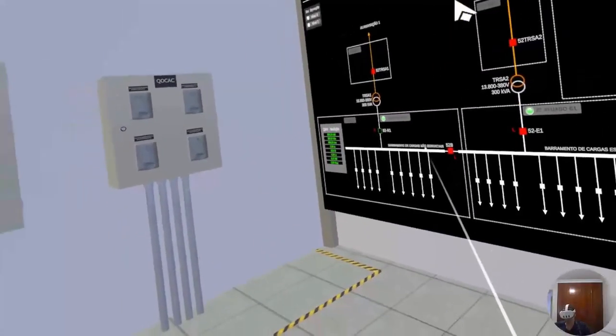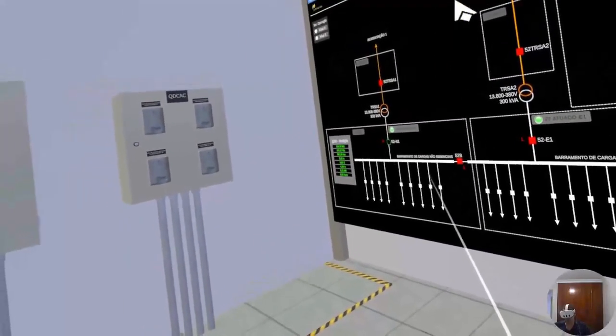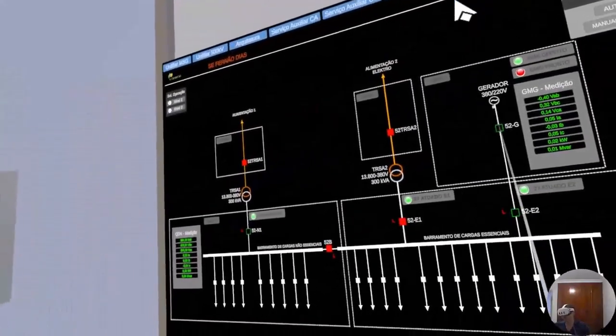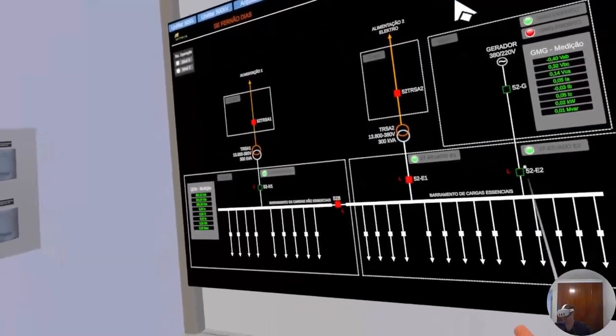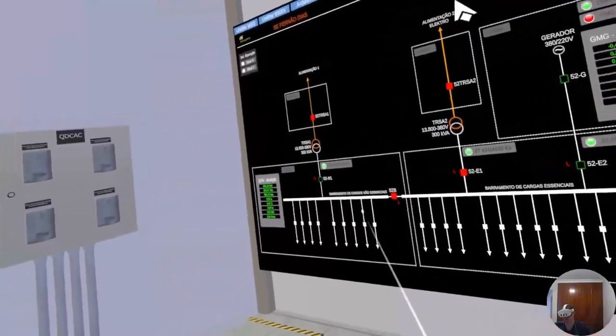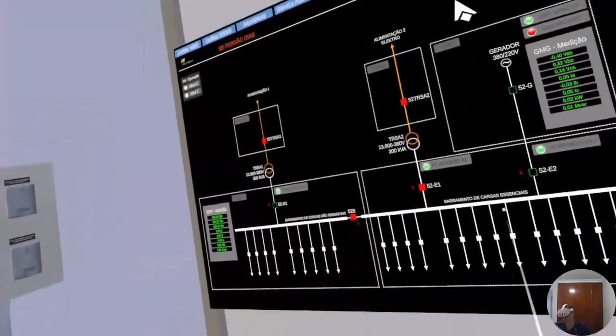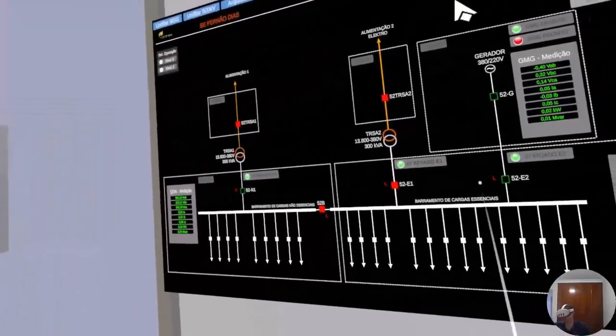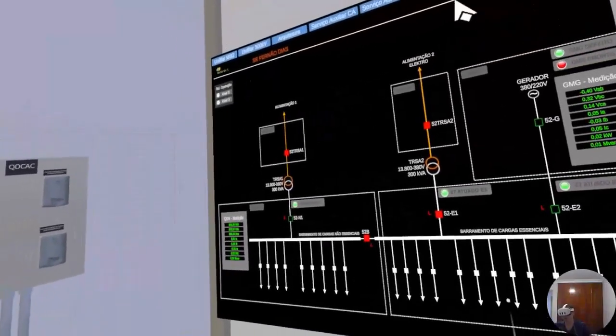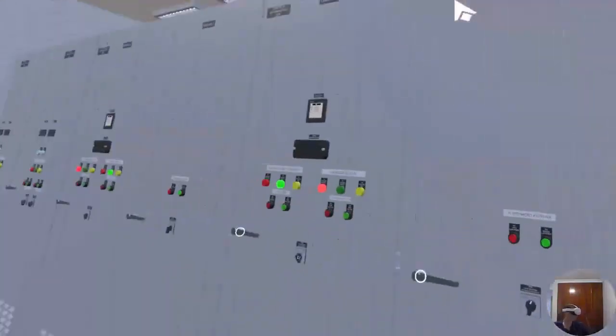Because otherwise, I'll be with the non-essential loads. I run the risk of overloading the diesel, so it will start the moment that I close this circuit breaker here. It will take the load, it could cause an overload on the diesel, and it shuts down. So to avoid this risk, I leave only the essential loads.